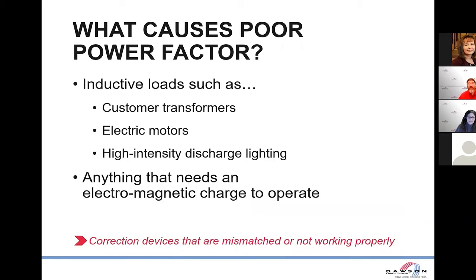Also, things that can affect power factor are like customer transformers. If you've got a big customer transformer, say, that's stepping down from 480 volts to 240 volts for an old grain dryer service, or a building you happen to have with your irrigation well or something, or maybe you plug a tractor in there in the winter. Those kinds of things can decrease your power factor also.